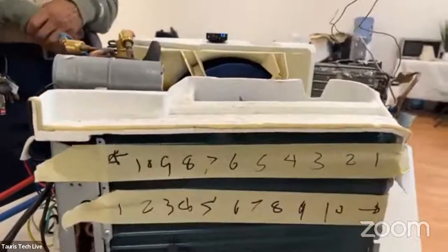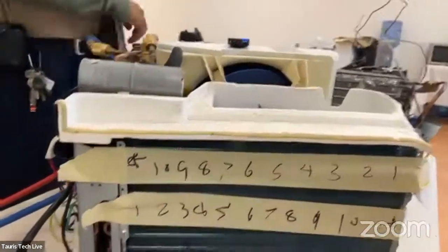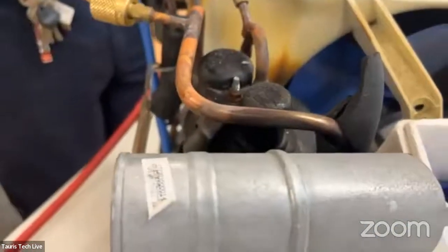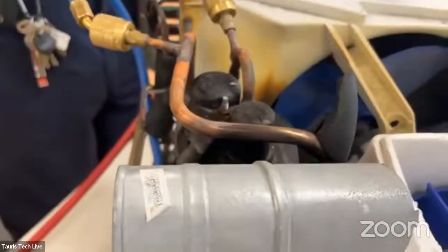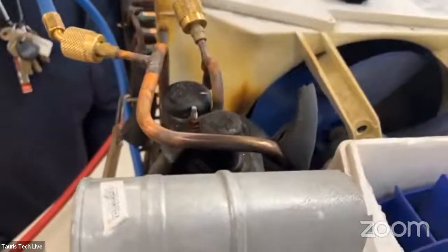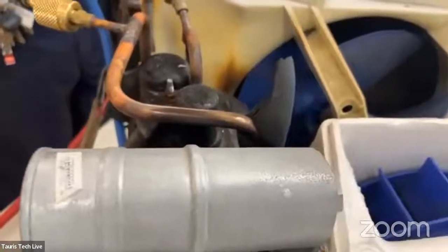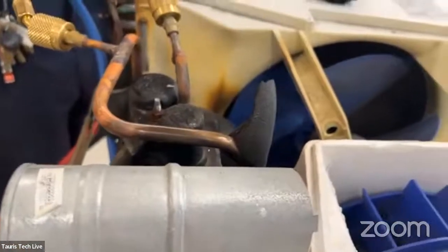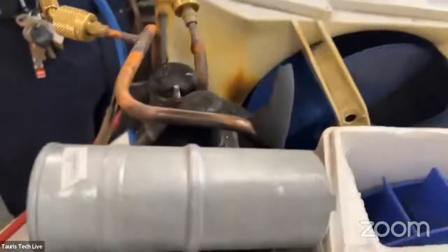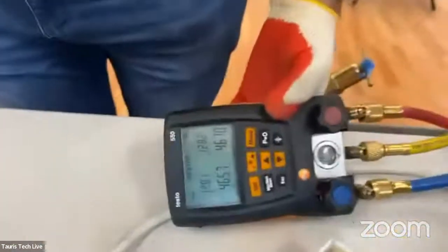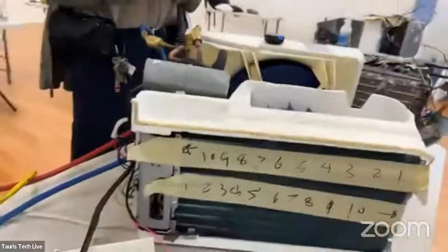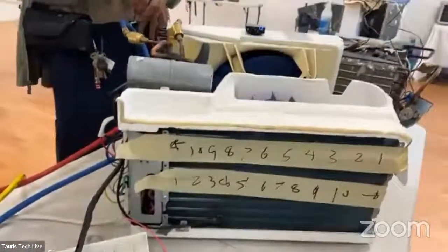Because if I'm boiling less in my evaporator, that means there is less what going over the compressor motor? Less refrigerant vapor. And now I'm not doing what with my compressor anymore? You're not keeping it cool. I'm not cooling my motor anymore. Correct. That's why all of this stuff is important. That's why we have to know what the pressures inside of my machine are, what my temperatures are, what my amperage is. All of this stuff is tied together.